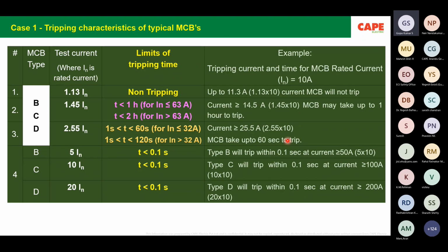MCBs, for example, there are 3 types of MCBs: B, C, D. Each one has a typical protective curve, especially for instantaneous tripping. Type B trips within 0.1 second if the current is more than 5 times its rated current. Similarly, type C 10 times, type D 20 times. Actually, these types, for example, to protect your wiring, we are supposed to use type B MCB. To protect a typical kind of equipment, you sometimes need C or D type of MCB. But for wiring protection, type B MCB is required.